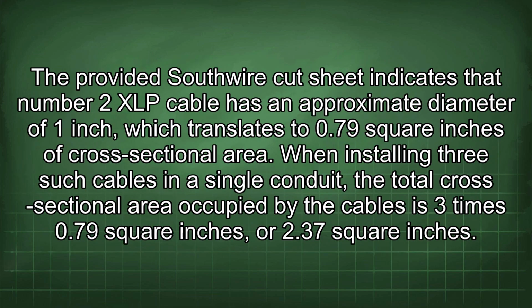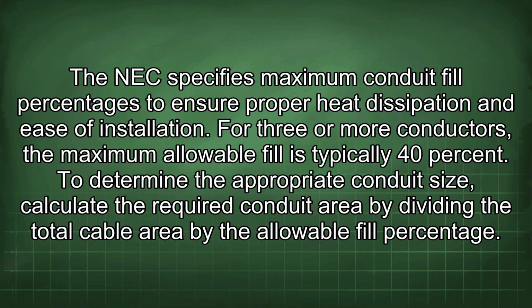The provided Southwire cut sheet indicates that number 2 XLP cable has an approximate diameter of 1 inch, which translates to 0.79 square inches of cross-sectional area. When installing 3 such cables in a single conduit, the total cross-sectional area occupied by the cables is 3 times 0.79 square inches, or 2.37 square inches. The NEC specifies maximum conduit fill percentages to ensure proper heat dissipation and ease of installation. For 3 or more conductors, the maximum allowable fill is typically 40%.